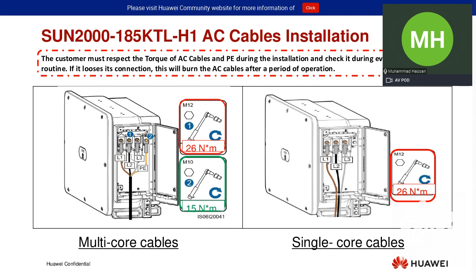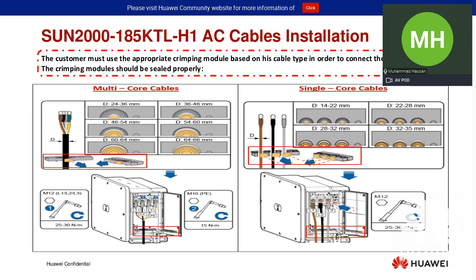Any one of you who goes to a site once the installer has finished the installation, just apply the torque settings onto the AC terminals to see whether the installer has applied the correct torque settings as per our recommendation. Otherwise, if there is less torque there, it will burn the AC cables very quickly during the production of that inverter.